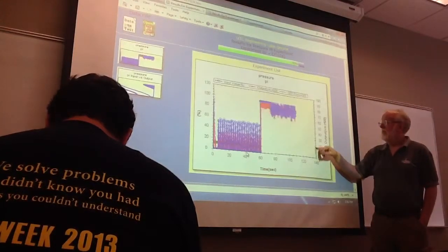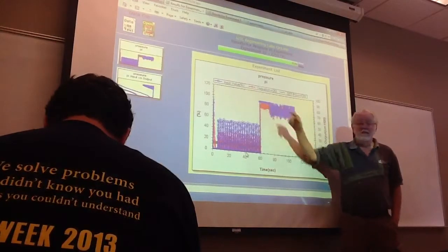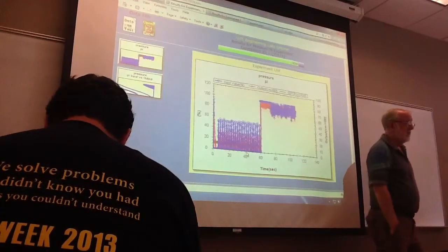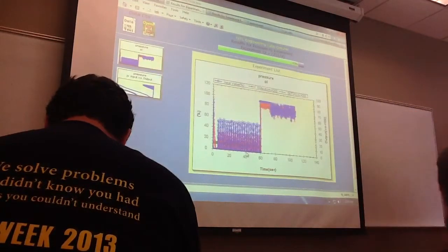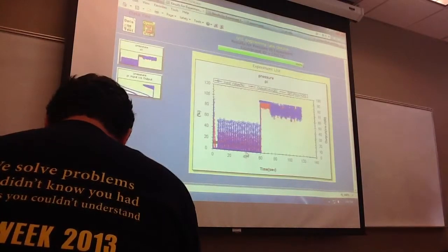You go from 10 up to 75 for the set point. So that's called wind up. It's an unfortunate condition that you don't like to have happen, because for 10 seconds there, it wasn't actually doing any controlling. It was all wound up.